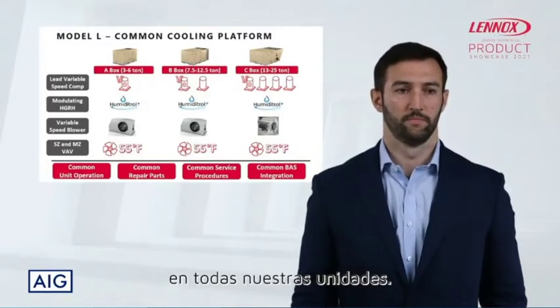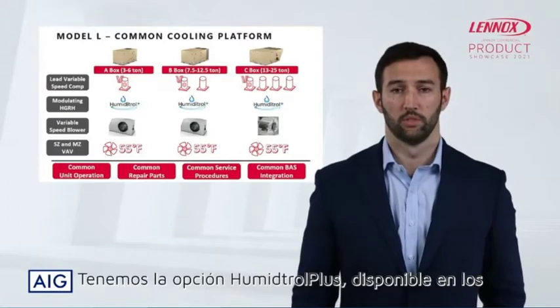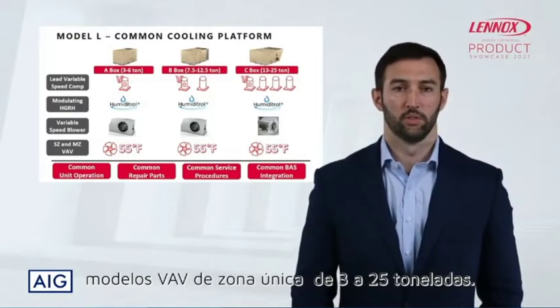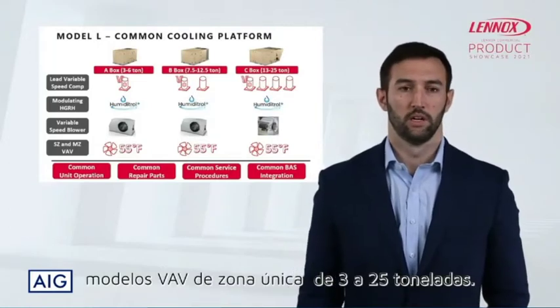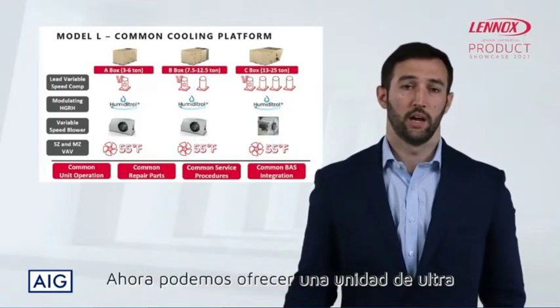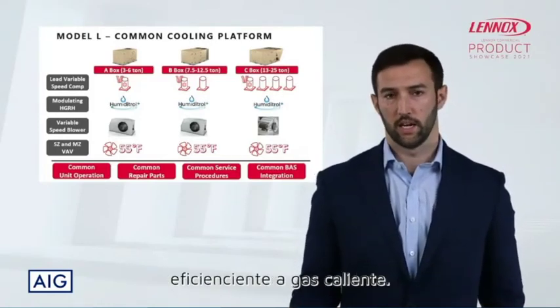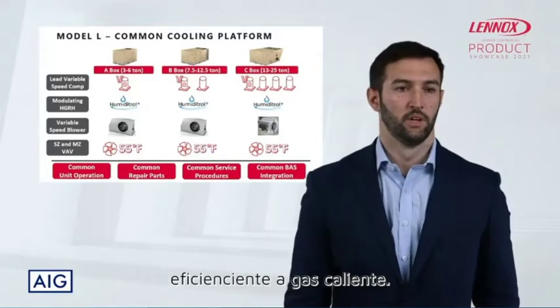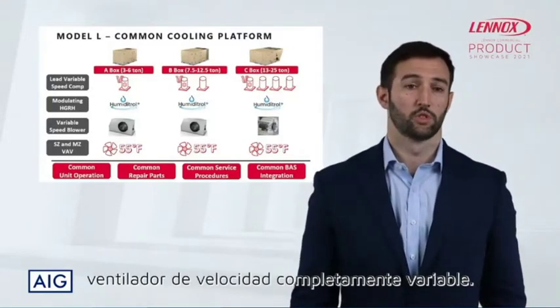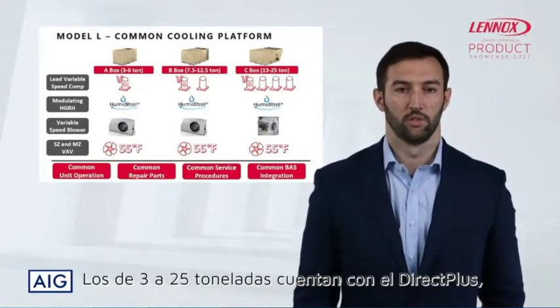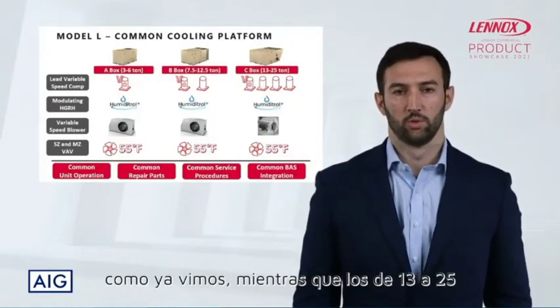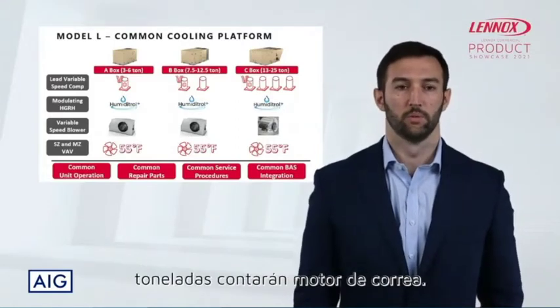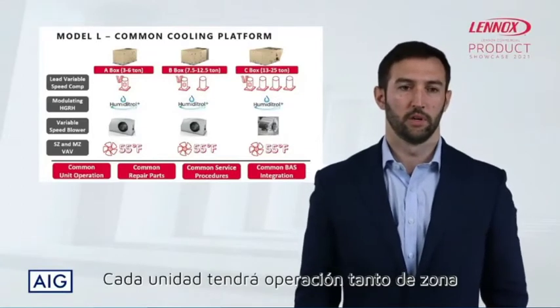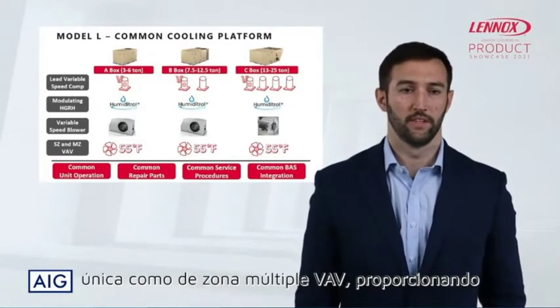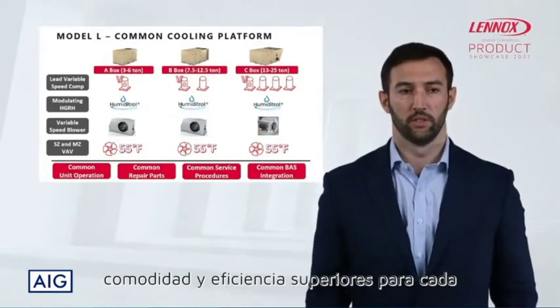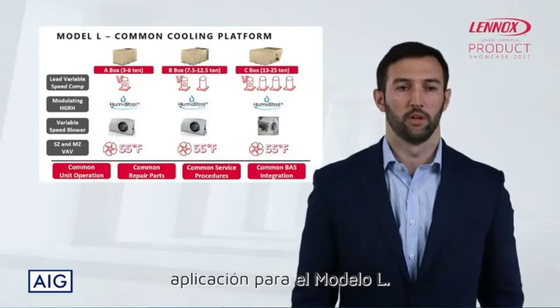The next is going to be the optional HumidiTrol Plus, which is available on all single zone VAV models from 3 to 25 tons. And so now we can offer an ultra high efficiency unit with hot gas reheat, which we were not able to before. So all Model L units feature a fully variable speed blower. So the 3 through 25 tons feature the direct plus blower, which we talked about, while the 13 through 25 tons will feature that BFD belt driven motor. And then each Model L unit will have both single zone and multi-zone VAV operation, and that's going to provide superior comfort and efficiency for every application we apply Model L.